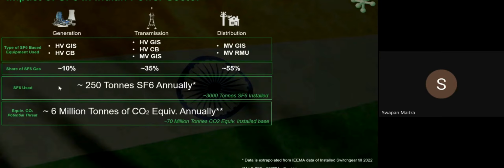And distribution networks are responsible for the majority of SF6 emissions. Immediate actions are needed: minimize the leakage, monitor emissions. If there is equipment, be it a stainless steel tank, within the stainless steel tank this SF6 is kept, and this interruption happens within this stainless steel tank. Still, there are leakages. As per IEC guidelines, the leakages should be restricted to 0.1% per annum. So there are leakages that happen.